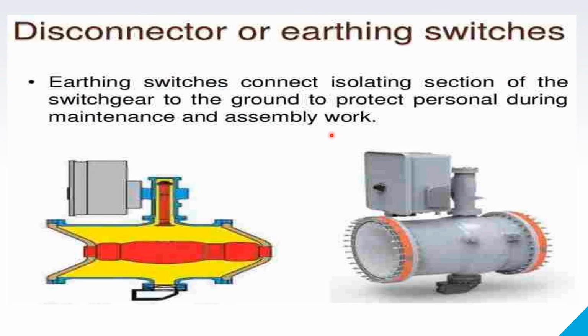Disconnectors or earthing switches are generally used at the substation level. Earthing switches connect the isolated section of the switchgear to the ground to protect personnel during maintenance and assembly work. So for the operators who are doing maintenance in the shutdown period or maintenance and operation cycle, the line should not get energized, so it is isolated using earthing switches.